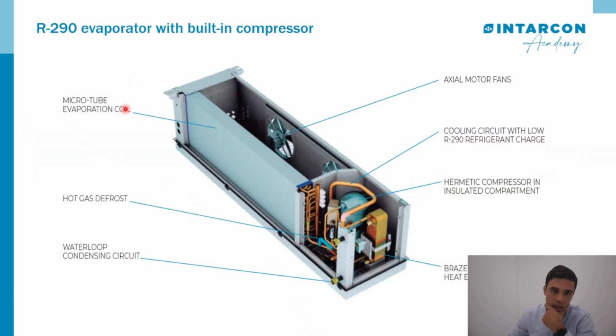Let's see a render of the microtube evaporation coil. Let's see the hot gas defrost line, the Waterloop condensing circuit, the inlets and outlets in this part, the plate heat exchanger, the hermetic compressor that is insulated from the other compartment. In this case, it is a scroll hermetic compressor. As a consequence of this compact equipment, we have a reduced R290 refrigerant charge. For example, the use of axial motor fans that are in the part of the evaporator.